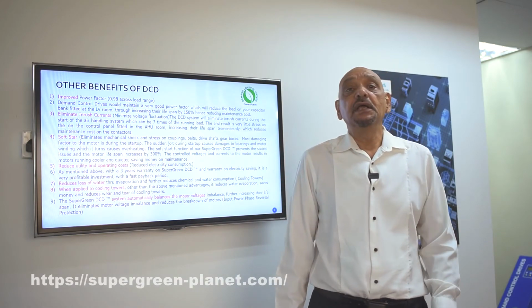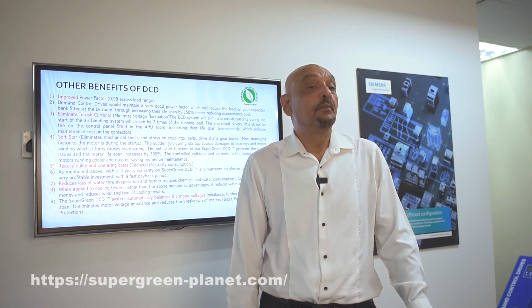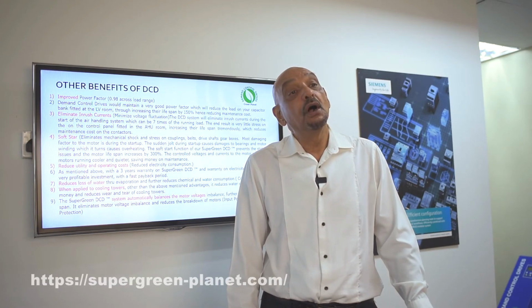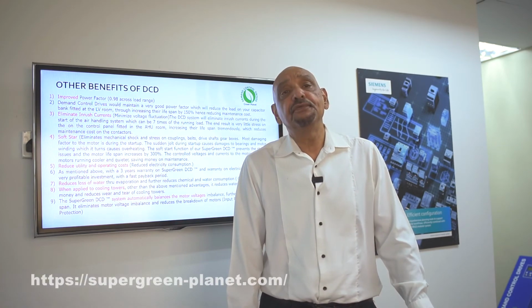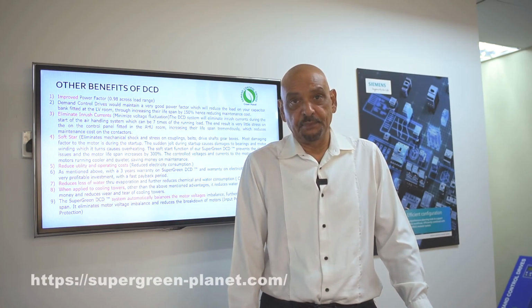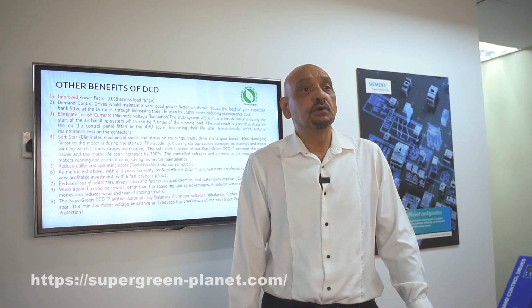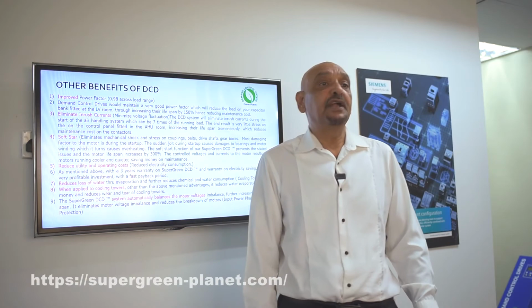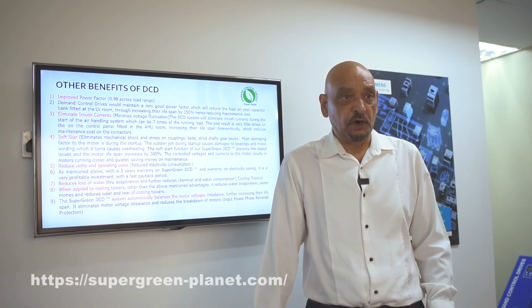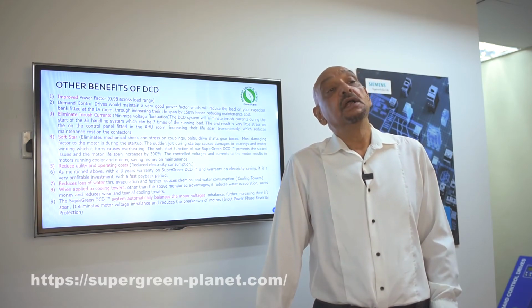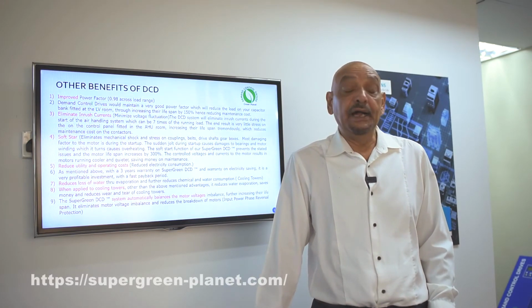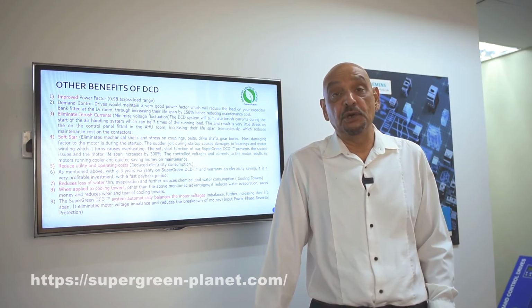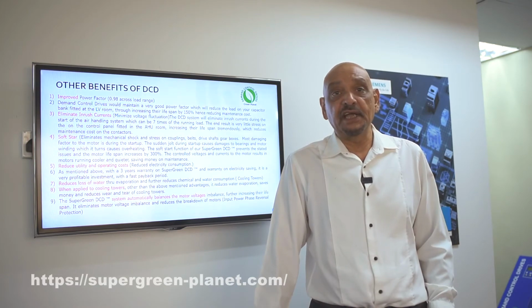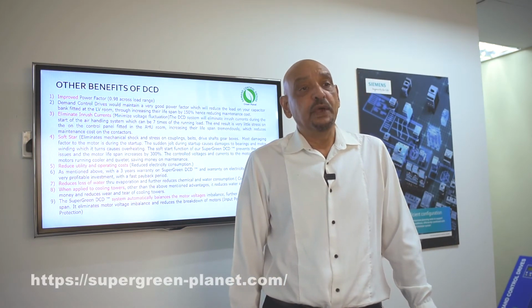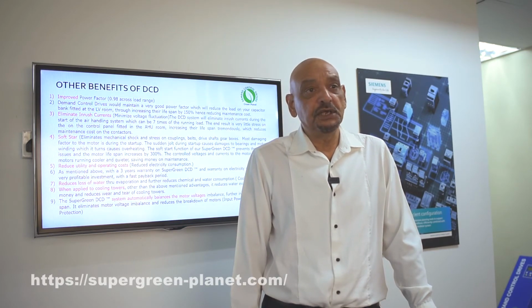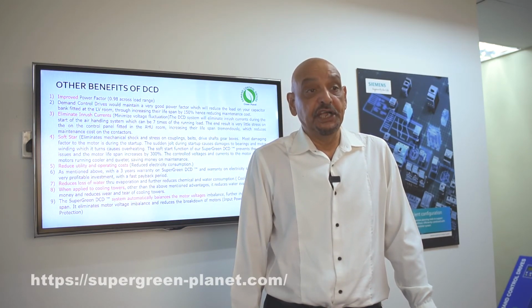Let's say, for example, in a standard inverter type configuration, doesn't matter how you install it, if there is a fault, for example, a motor fault, the whole system will stop and wait for your in-house technician to respond. As far as the DCD is concerned, whether it's a permanent or temporary fault within your motor itself, the DCD will detect that and immediately shut down your system, wait for 20 seconds, then slowly start up your system and monitor again.